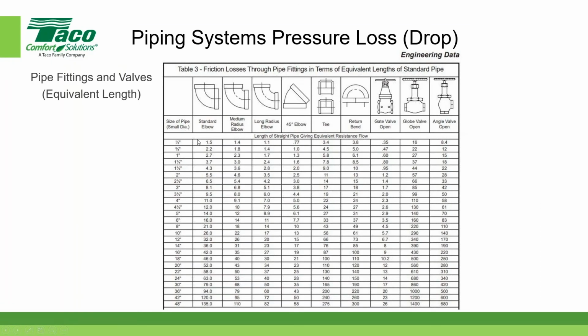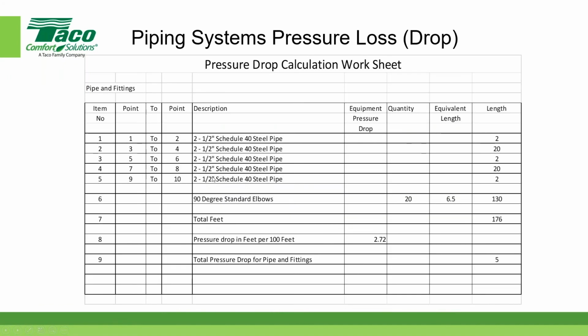Going back to our chart, for a 2.5-inch pipe, a standard elbow has the equivalent length of 6.5 feet. So again, coming back to my table, I have 20 elbows at 6.5 feet. I simply multiply 6.5 by 20, and now I have the equivalent length of 130 feet. So above is the length of the actual sections of pipe, and now I have the equivalent length for the elbows.